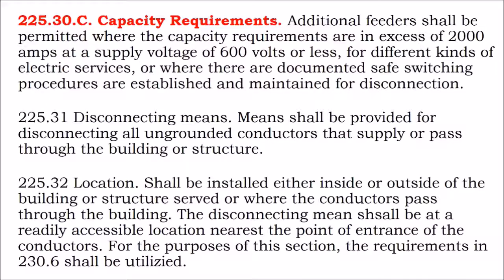And in the past, this disconnect requirement has been very confusing because there's also the utility disconnect, which really, when it boils down to it, it says it can be located outside the building or inside at the first available spot. Really what utilities want is a disconnect on the side of the building that they can use to turn off your on-site power systems. And maybe that'll be multiple disconnects for when you get into having a solar array and an electric vehicle charging station, something like that.